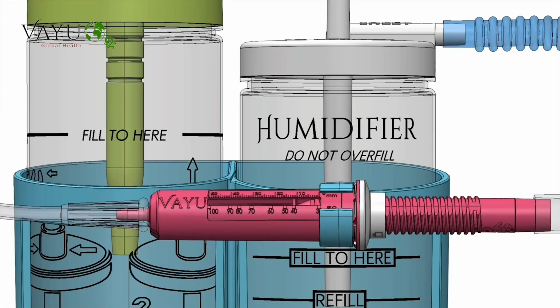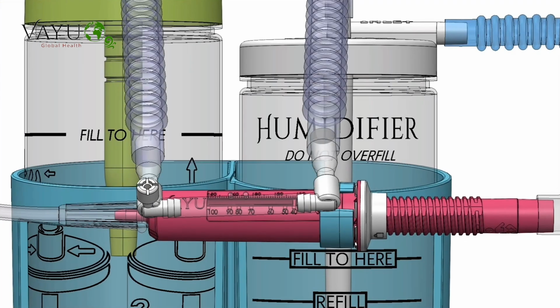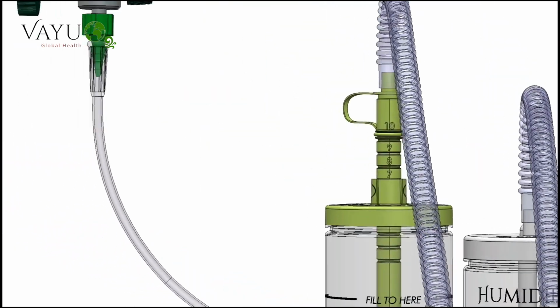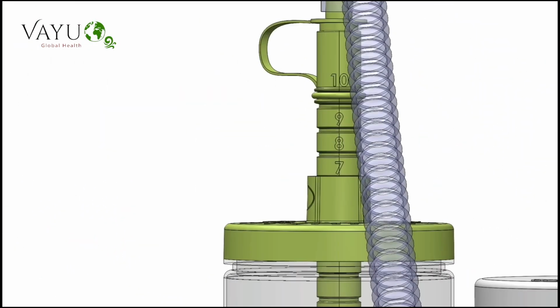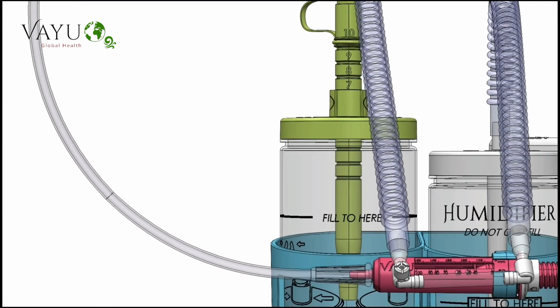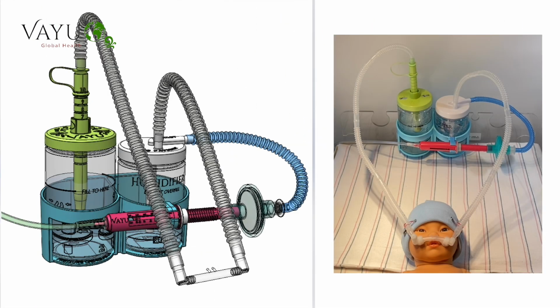Now that the gases are blended, filtered, and humidified, they are ready for the patient to breathe through a pair of silicone binasal prongs. The gases then flow into the pressure generator, which generates pressure to keep the baby's lungs open. This can provide from 4 to 10 centimeters of water pressure, depending on the depth of the wand. The device can be seen bubbling, which means that it's working and the patient is receiving respiratory support.